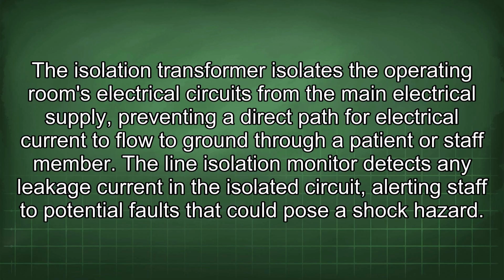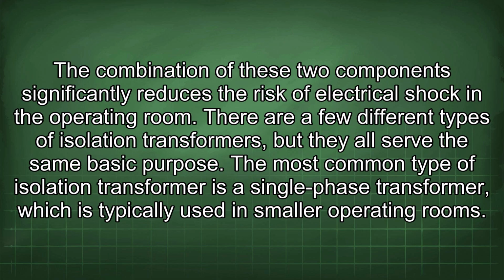The line isolation monitor detects any leakage current in the isolated circuit, alerting staff to potential faults that could pose a shock hazard. The combination of these two components significantly reduces the risk of electrical shock in the operating room. There are a few different types of isolation transformers, but they all serve the same basic purpose.